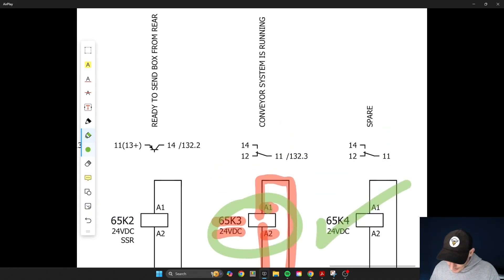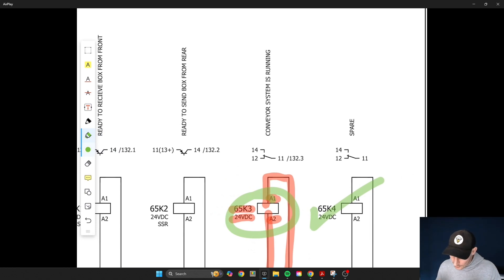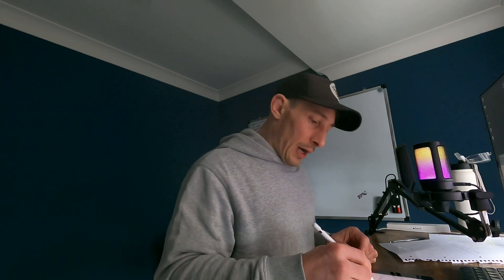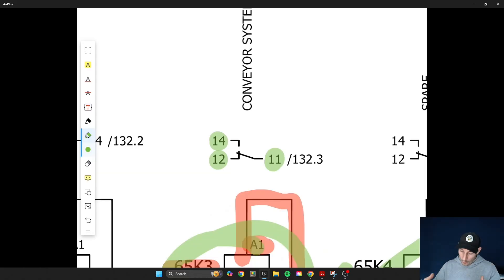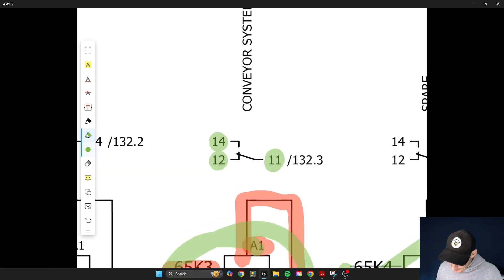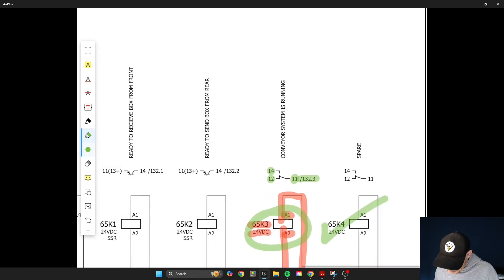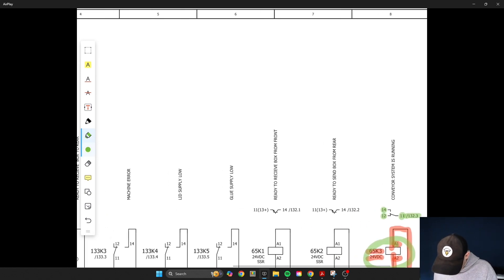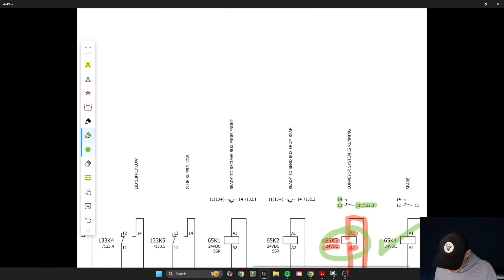When that machine sends out that signal it will energize that relay and switch it on or off depending on what's happening on the contact side. This is where you get more detail. It's a single pole relay, always labeled the same way — terminal 11 is the common, terminal 12 is normally closed, and terminal 14 is normally open. To find the contact side, you can see here it says slash 132.3, meaning it's on page 132, column 3.